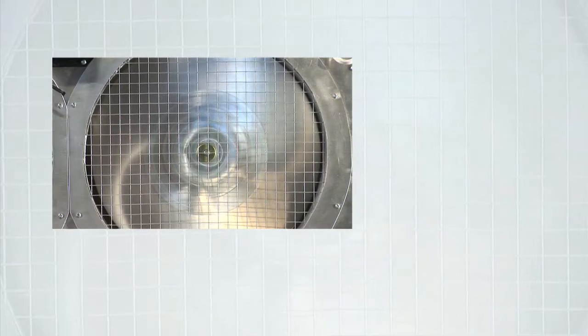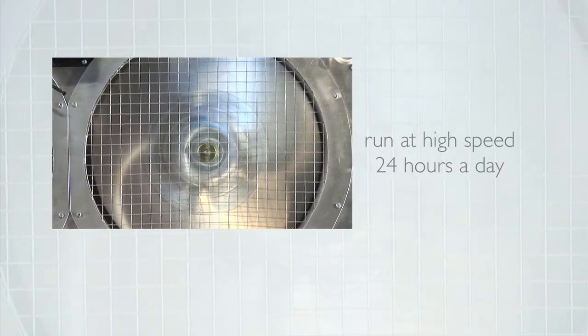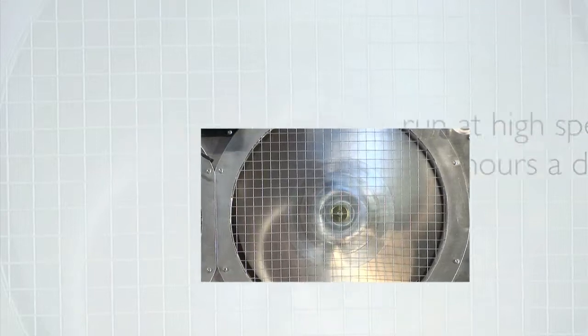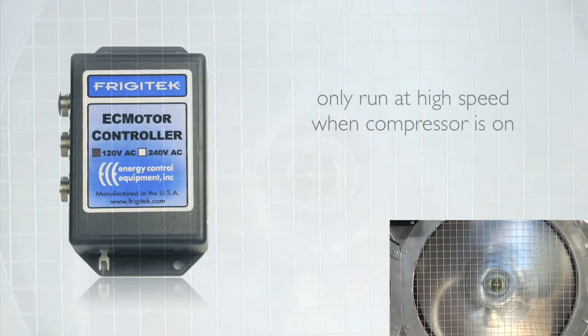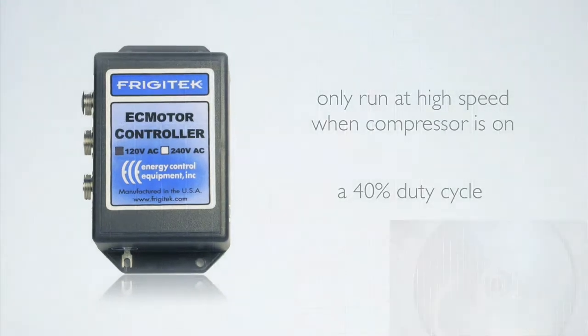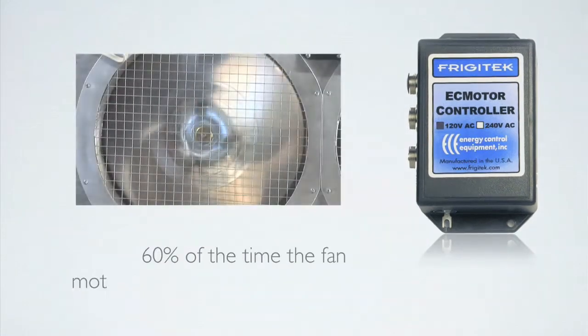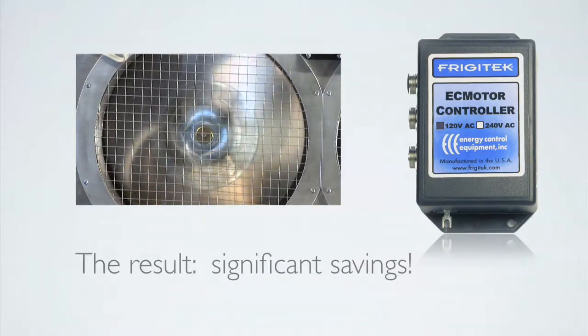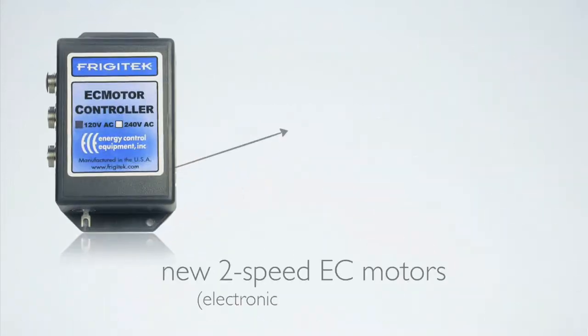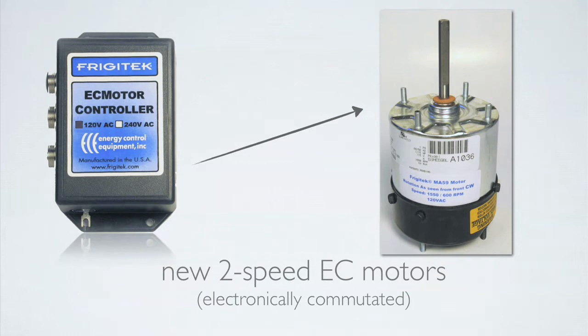These motors run at high speed, consuming electricity 24 hours a day, but they don't need to. With a Frigitek controller, the fan motors will only run at high speed when the system compressor is operating, which for most units is about 40% of the time. This means that for the other 60% of the time, the fan motor RPM can be lowered dramatically while still providing the necessary airflow in the box. The result? Significant savings. Frigitek works in conjunction with the new 2-speed EC motors that are far more efficient than the shaded pole motors currently found in most walk-ins.